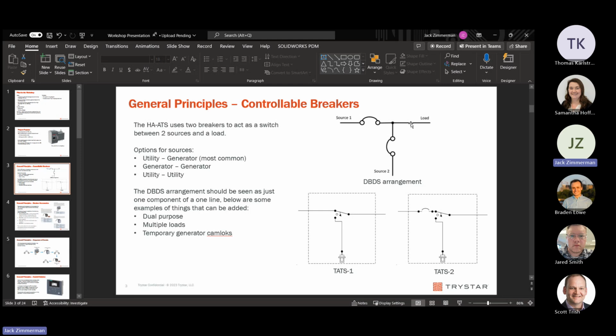Could you just have a renewable source coming in on one side? It's possible, but renewables like to have strange waveforms when they aren't being led by a generator or utility, which might cause some strange behavior with the controller. Because they're not directly creating a true sine waveform, they're doing like a PWM version where they're flipping switches on and off. So it's possible, but it's not fleshed out by Siemens, who's the manufacturer of the controller.